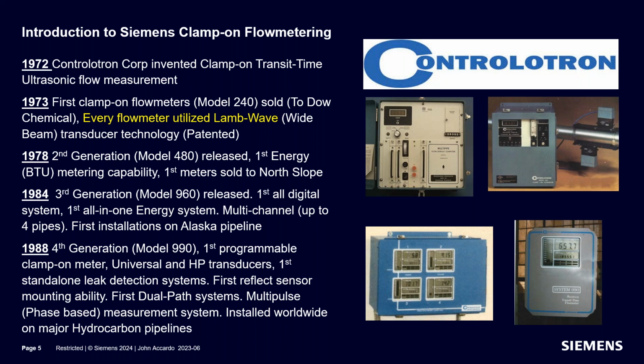Up until the release of the 990, as I said, every flow meter came with Lamb wave transducers. That was the only way the flow meter was delivered. And as we go through this, we'll talk about what makes a Lamb wave transducer a Lamb wave transducer. But specifically, it's fit to the pipe, more or less. It's matched to the pipe that you're measuring.